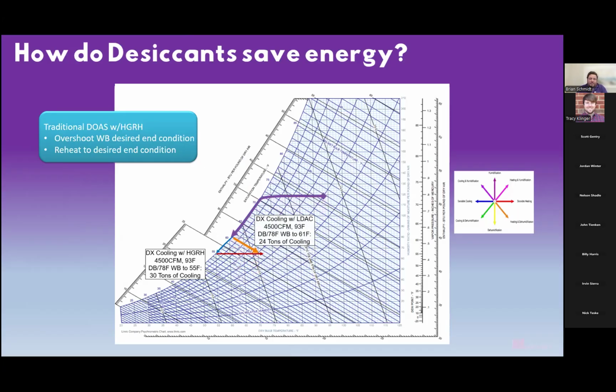So the way that we could conserve energy is instead of driving down to 55, what if we went down to 61, hypothetically? If we drive down to 61 degrees and then reheat it with hot gas reheat, we're not going to hit our space condition. However, if we allow liquid desiccant to take over the dehumidification process, we can follow this line of enthalpy down to our space condition. The more of this little triangle at the bottom that you can cut off, the more energy you save. Because again, as I mentioned, every line of enthalpy you cross over is exponentially more intensive and costs more money. So on a peak load day, we do have a DX system. We're going to drive down to, again, 60, 61 degrees, and then we're going to allow the liquid desiccant to take over the dehumidification process.